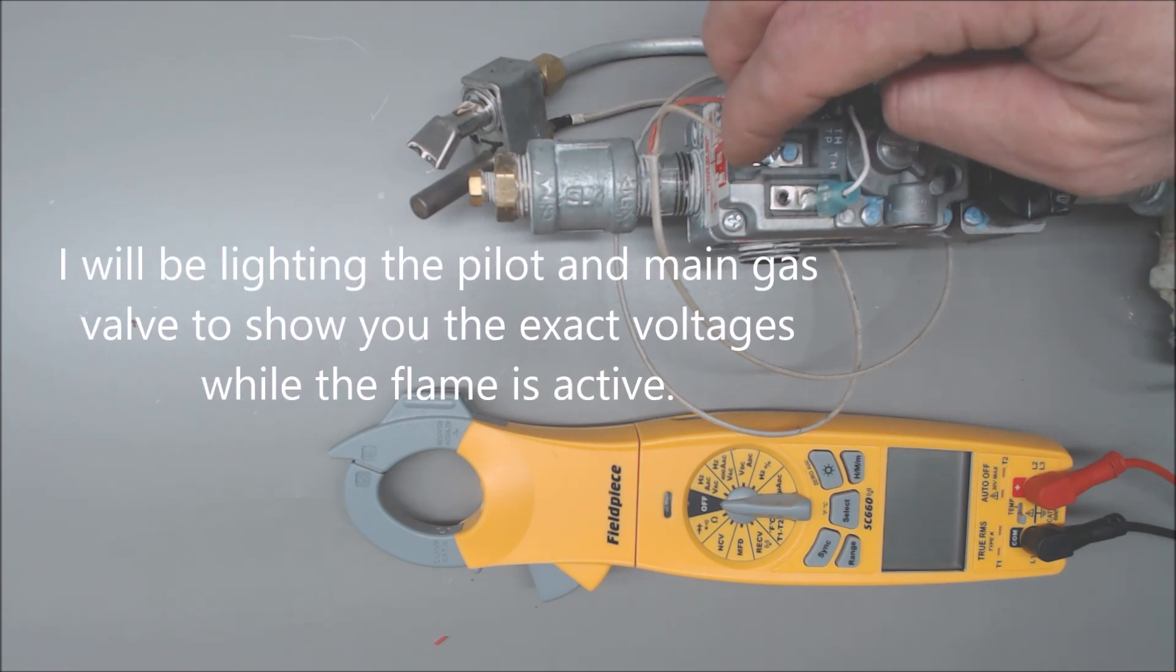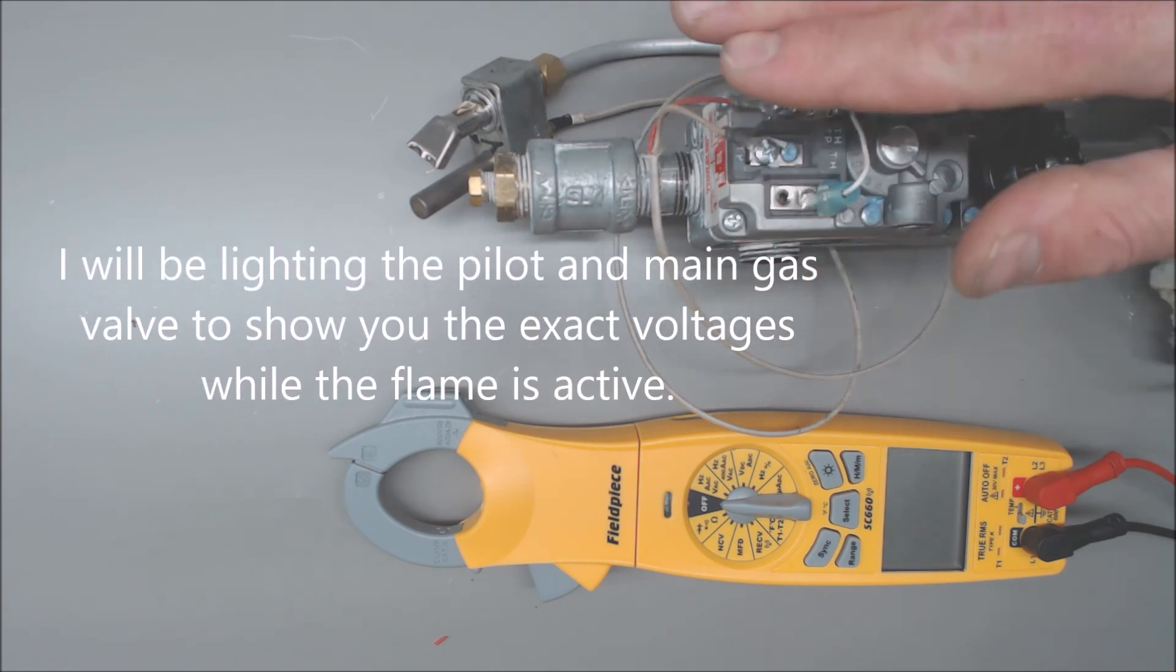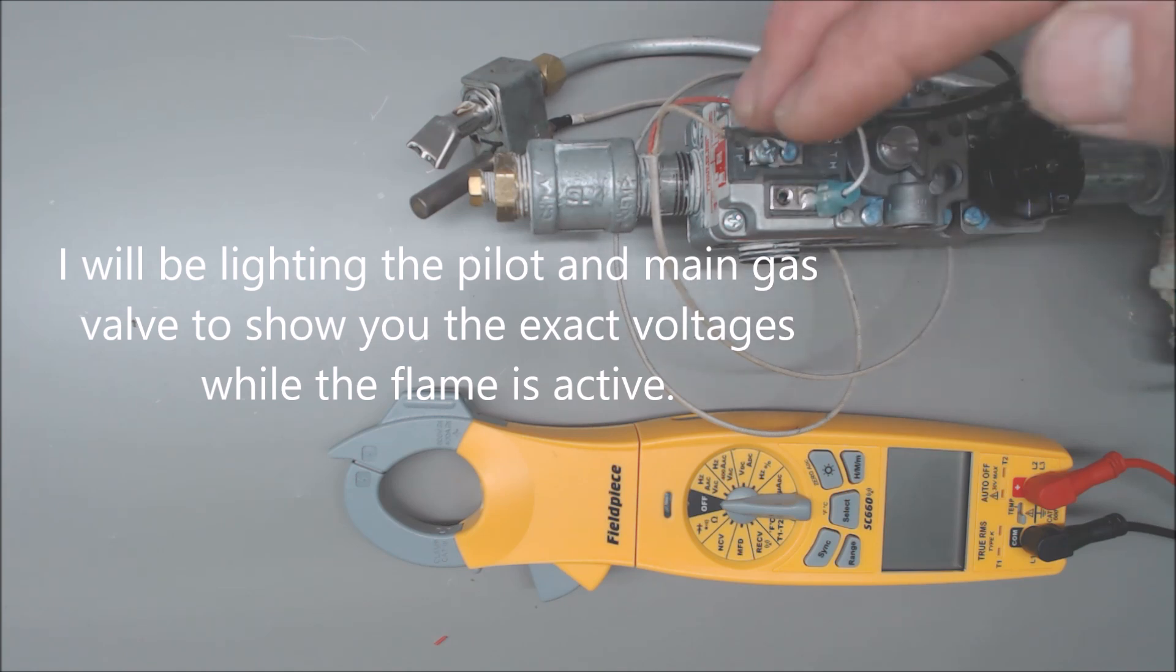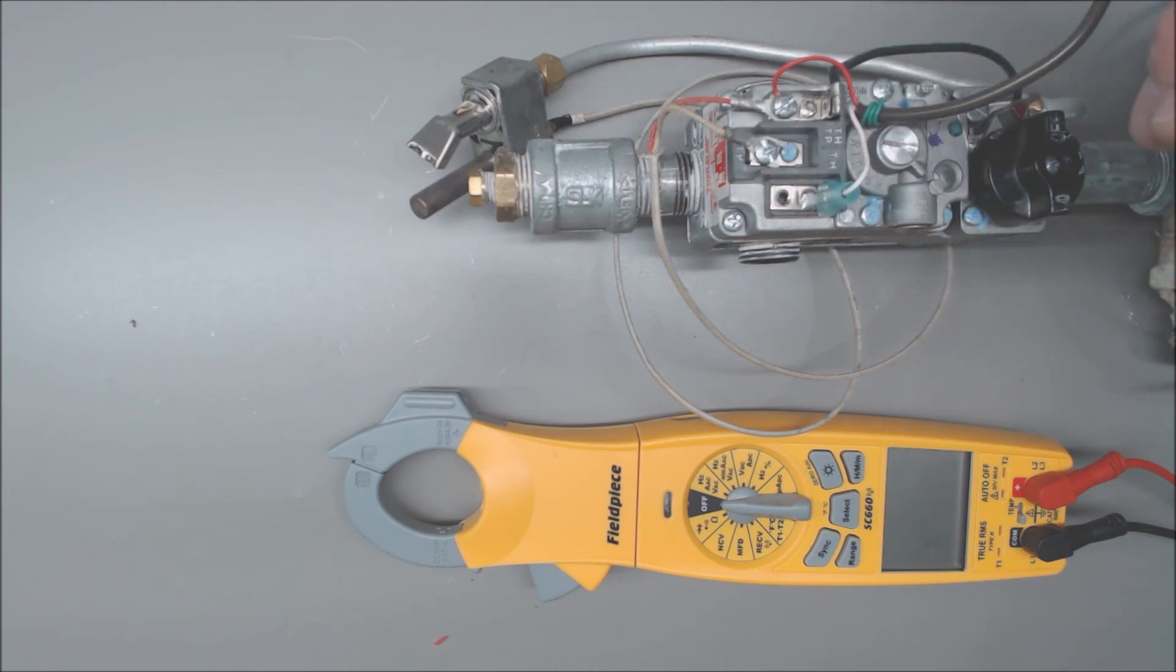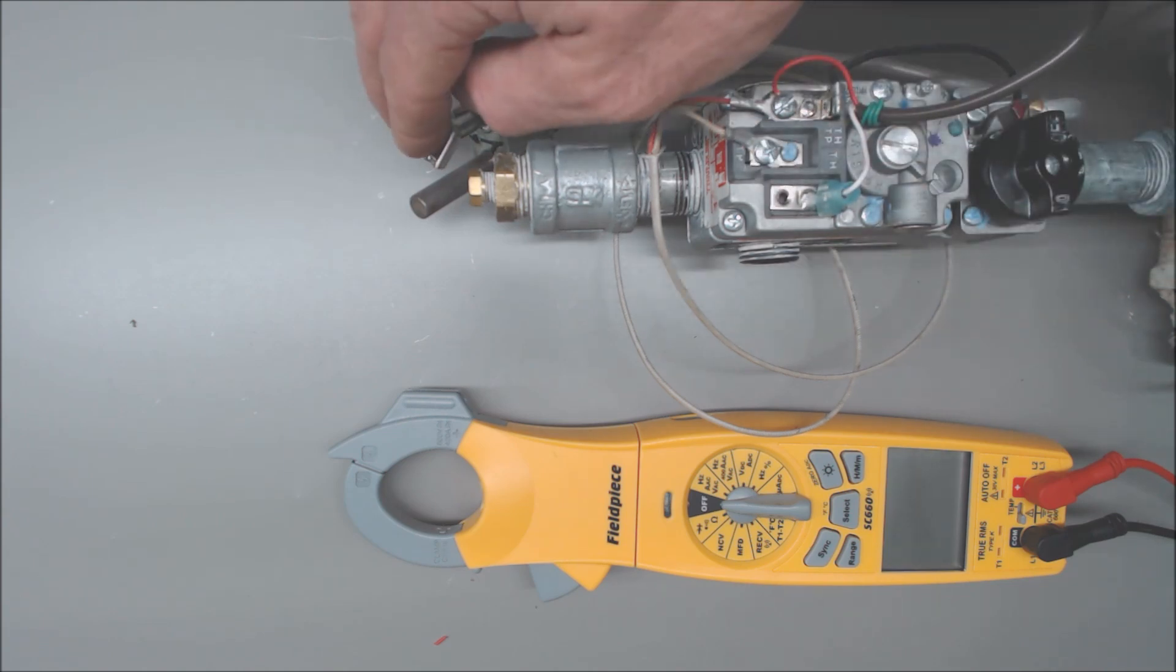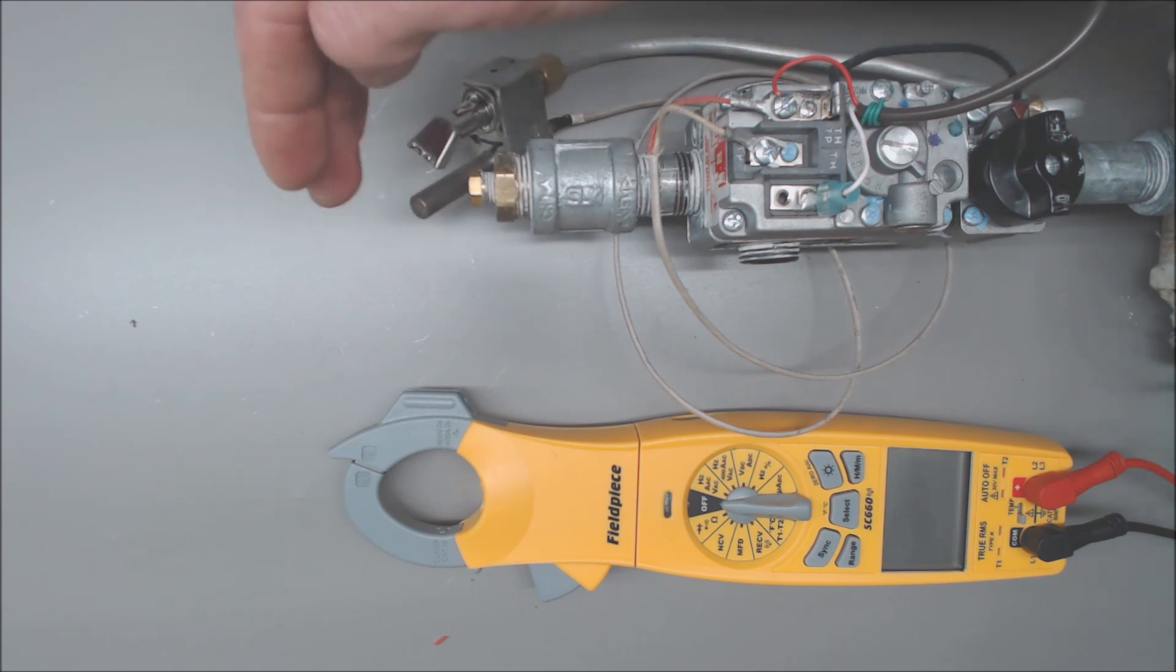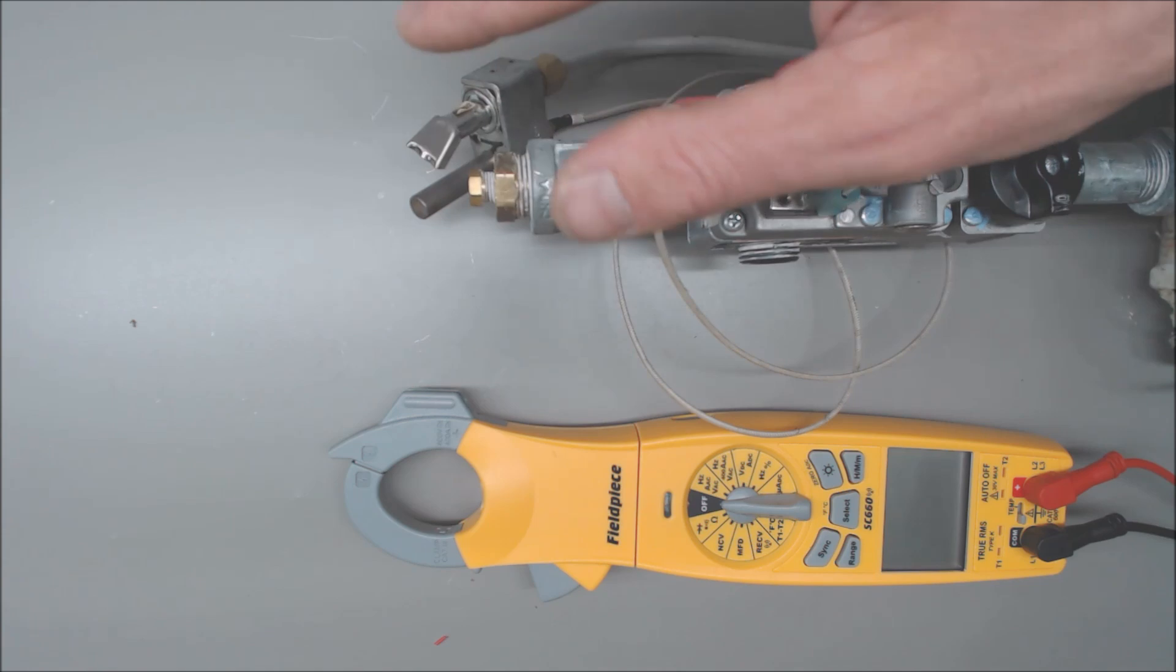On your pilot valve, you need at minimum 50 or 60 millivolts DC, but preferably more, around 100 to 200 millivolts DC. The whole point is that when the flame is heating your thermopile, you're able to generate around 750 millivolts or just a little bit lower.